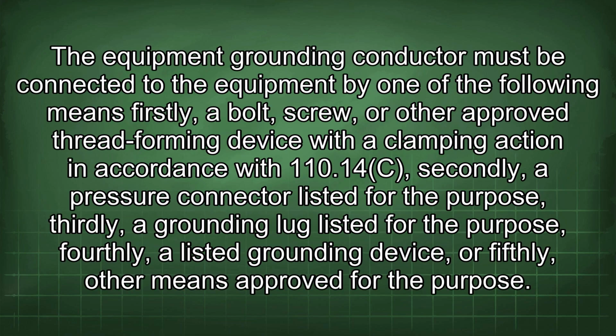The equipment grounding conductor must be connected to the equipment by one of the following means: firstly, a bolt, screw, or other approved thread-forming device with a clamping action in accordance with 110.14(C). Secondly, a pressure connector listed for the purpose. Thirdly, a grounding lug listed for the purpose. Fourthly, a listed grounding device. Or fifthly, other means approved for the purpose.